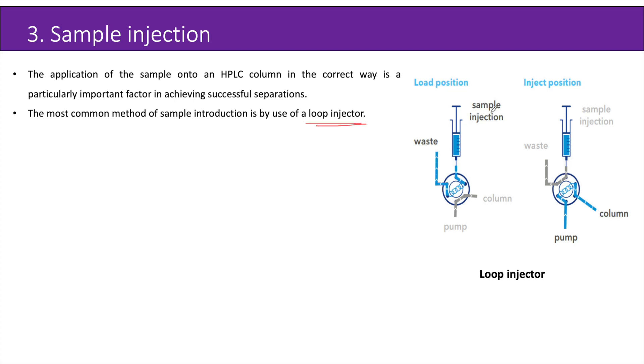The next step is sample injection. The application of the sample onto an HPLC column is a particularly important factor in achieving successful separations. The most common method of sample introduction is by use of a loop injector. In the load position the sample is within the sample injector, and in the inject position the sample is transferred via pump into the column.